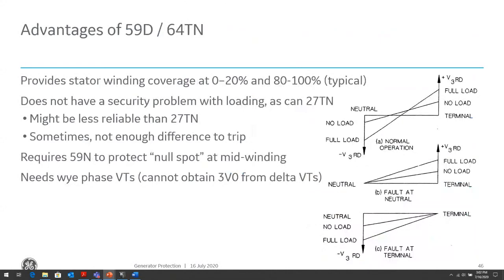So the advantages of the 59D or 64TN over the 27TN, as I mentioned, it can provide full coverage, and the security is not so much of a concern, but it can be less reliable than the 27TN. The third harmonic voltage magnitude is measured in the machine neutral via an auxiliary transformer. And then that 3V0, or the zero sequence voltage magnitude, is measured from the terminal side of the transformer. So in that case, we either need a broken delta connection to be able to measure that 3V0, or we need a Y connected VT on the terminal side. Whereas in the 27TN, we only need to measure the neutral voltage to get the third harmonic from the neutral voltage.